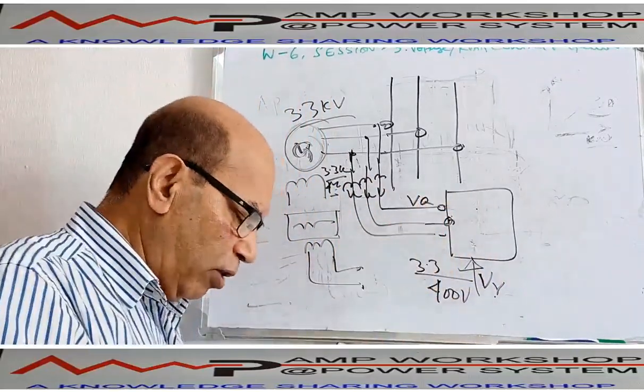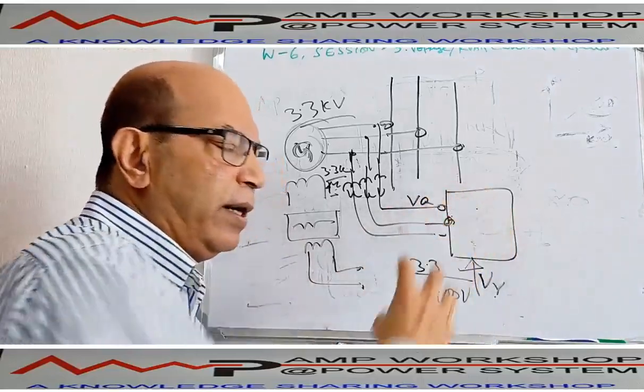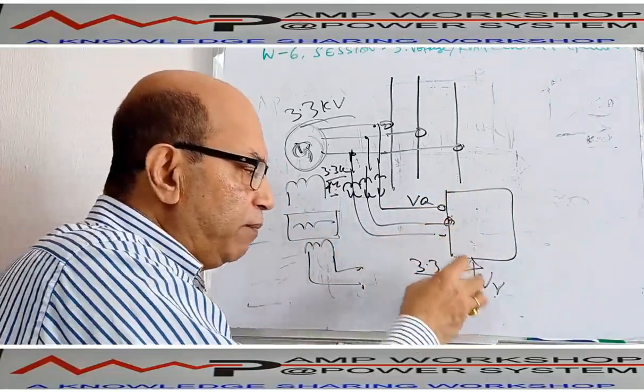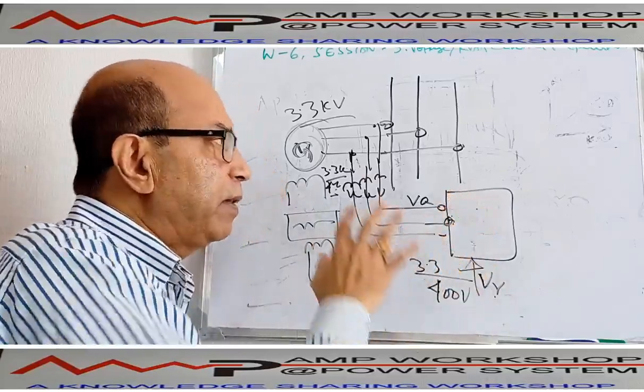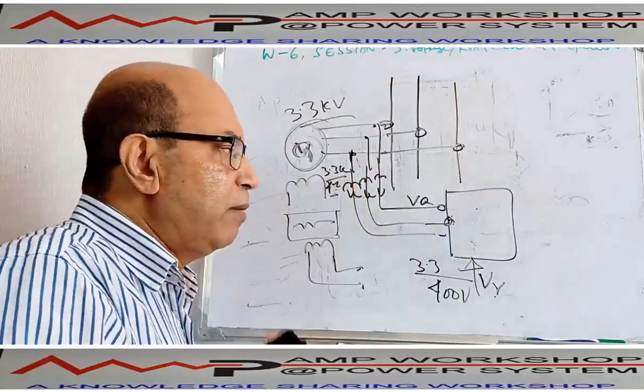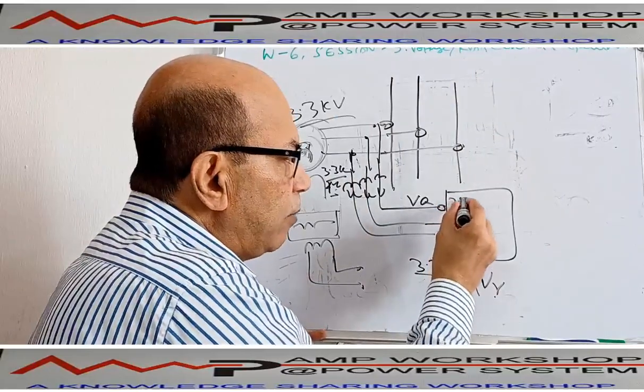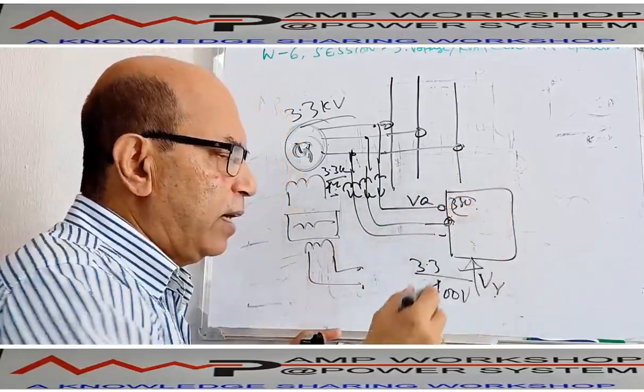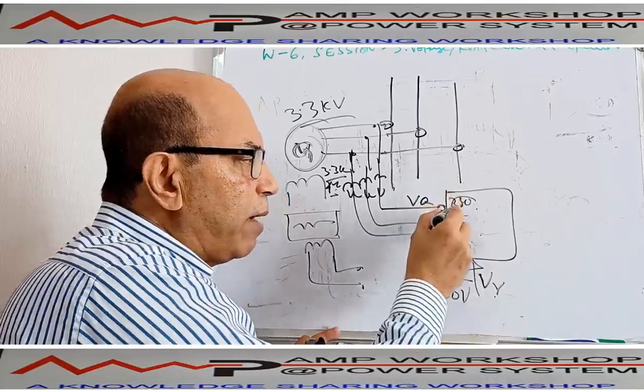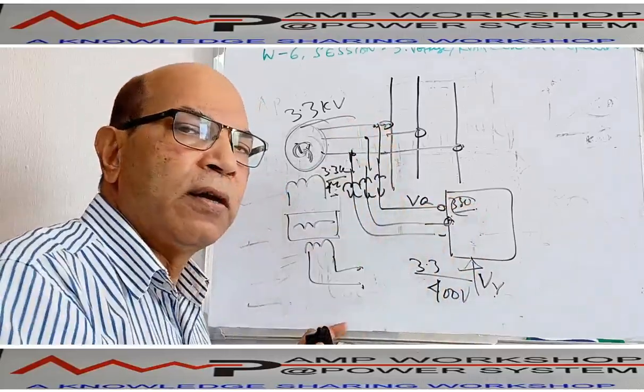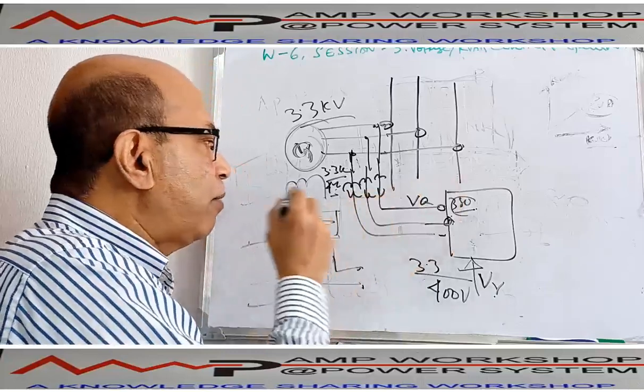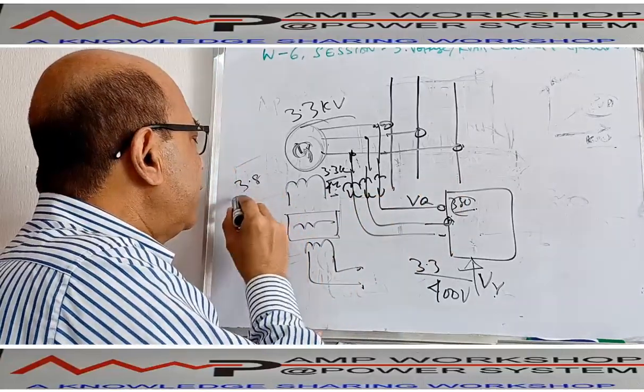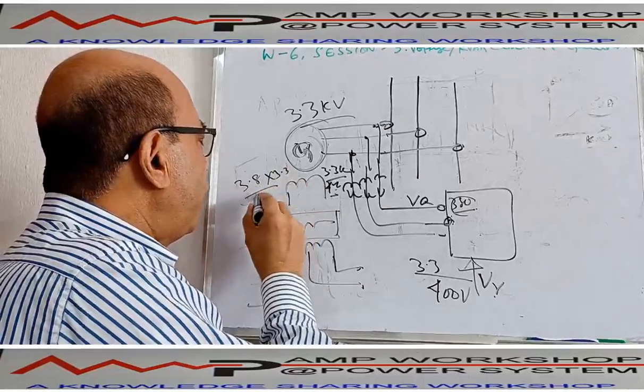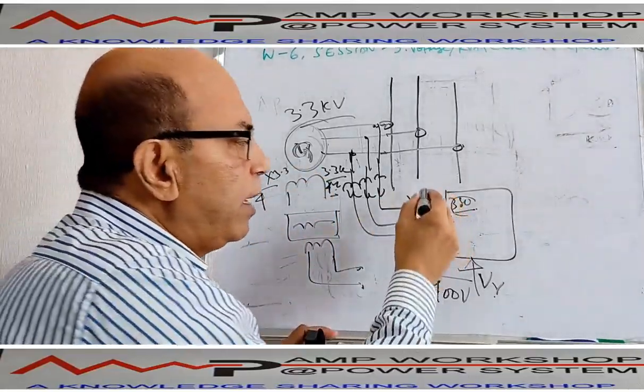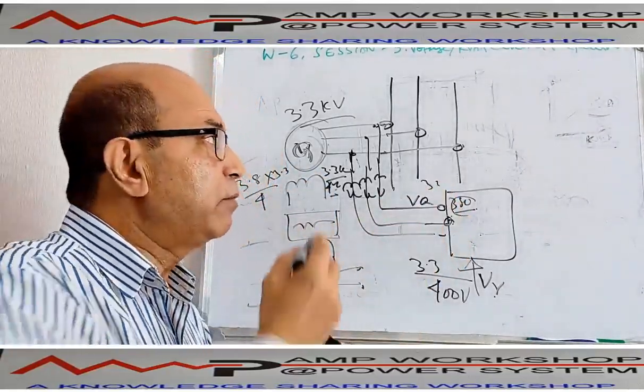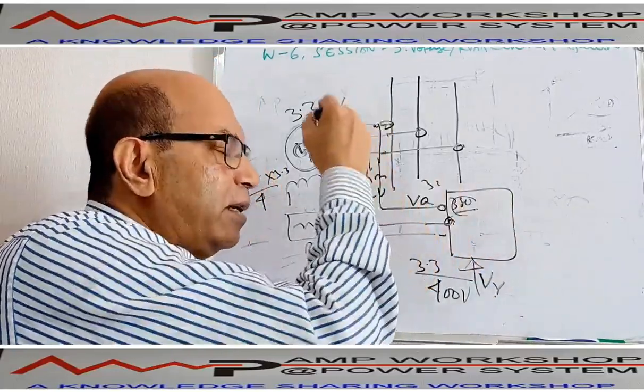Once we give the reference voltage, then this equipment has a brain. So it knows if this 400 volt comes as an input, then this voltage is produced by 3.3 kV. The moment, suppose the voltage comes down to 380 volt, then immediately the equipment will understand, I am supposed to get 400 volt, now I am getting 380 volt. That means the voltage is not 3.3 kV. The voltage is proportional, so it will be 3.8 into 3.3 by 4. So this will be the ratio. So maybe it is 3 kV. So immediately this equipment will understand there is a voltage drop.